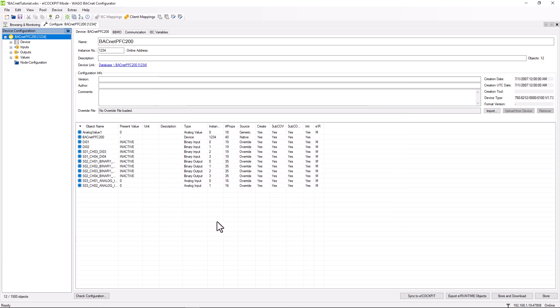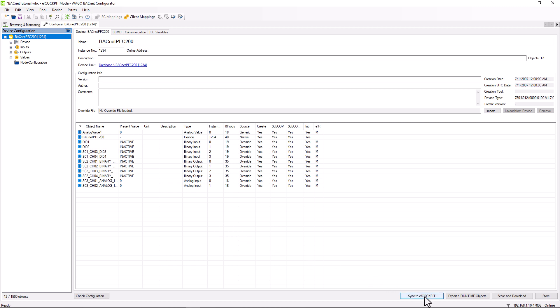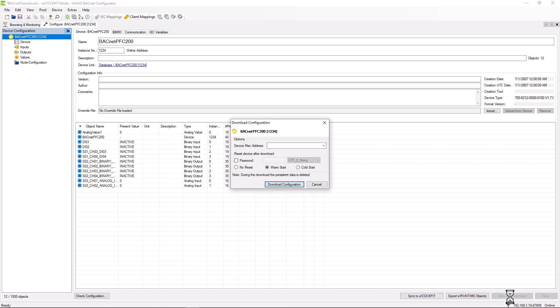The list now shows the analog value as a BACnet object. To be able to use all the objects in CODESYS, we have to synchronize them with a button that is still called 'Sync to e!COCKPIT' in this version. With 'Store and Download', we store the configuration in the BACnet configurator project file and in the BACnet stack of the controller. This completes the configuration in the BACnet configurator.